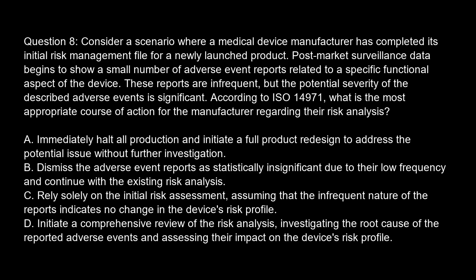Question 8. Consider a scenario where a medical device manufacturer has completed its initial risk management file for a newly launched product. Post-market surveillance data begins to show a small number of adverse event reports related to a specific functional aspect of the device. These reports are infrequent, but the potential severity of the described adverse events is significant. According to ISO 14971, what is the most appropriate course of action for the manufacturer regarding their risk analysis?